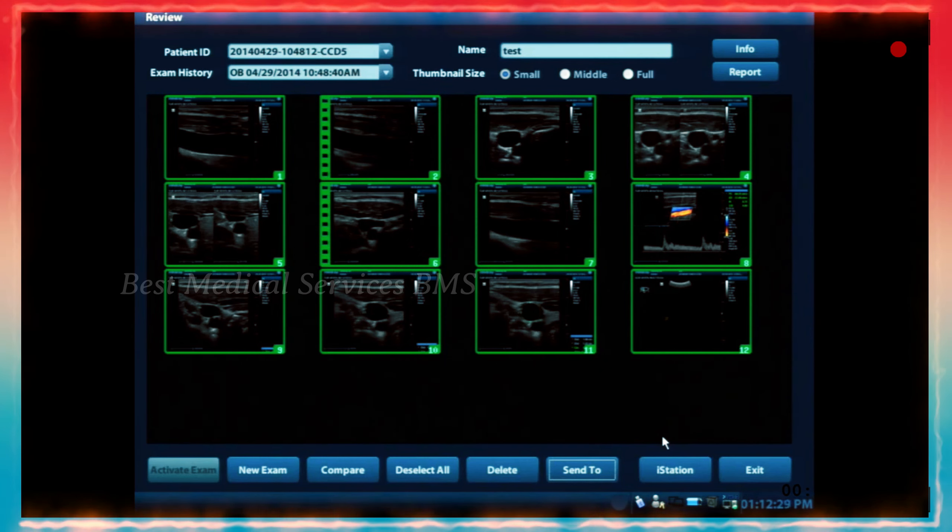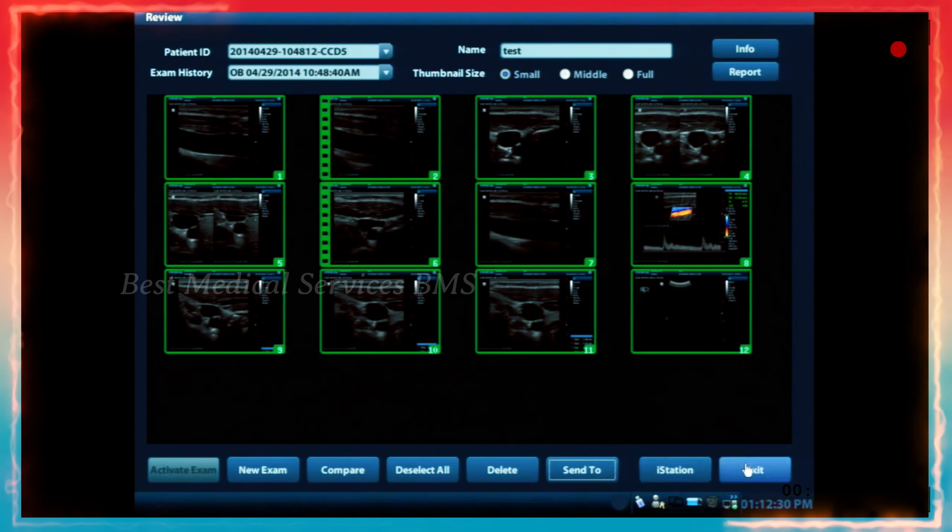When you're ready, click the okay button. At the very bottom you'll see task management — hover over it and click. You can see the arrows indicating transfer progress, showing your study name, patient name, destination, content, and date. You can exit while it's transferring. This is a good way to know if you're sending multiple studies and how long it's taking depending on the images and cine clips stored.